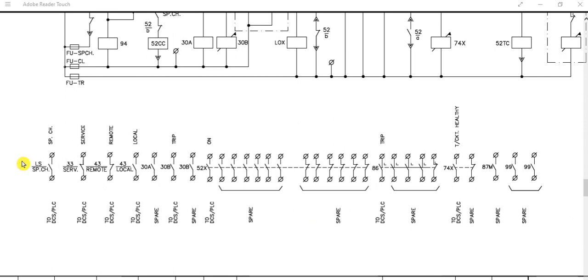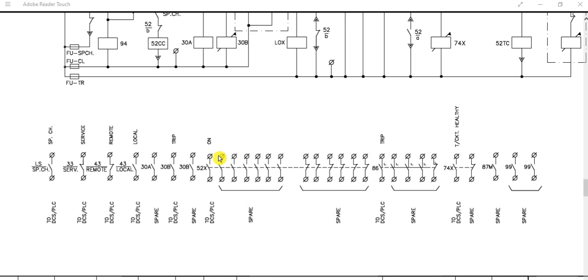These are the digital inputs (DI) to communicate with DCS or PLC: limit switch spring charging motor, breaker in service position, control switch location, and local/remote selection switch feedback. Circuit breaker ON, OFF, trip, and balance are spare contacts available. Trip circuit handling is through 74X. 87M is the spare for the differential element. 99 is for motor protection along with the motor protection delay contact.